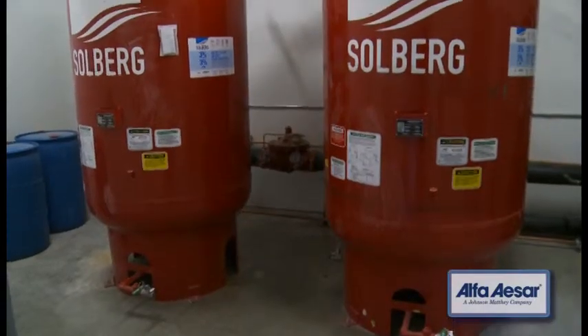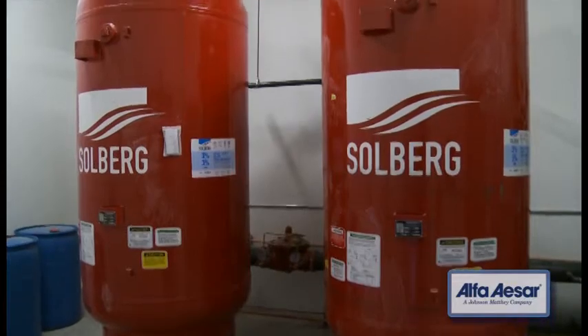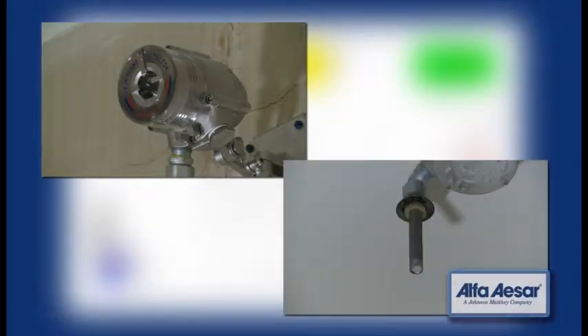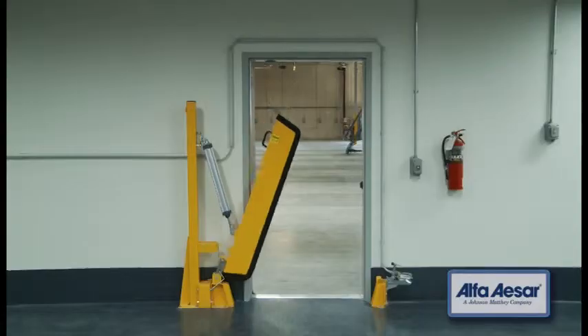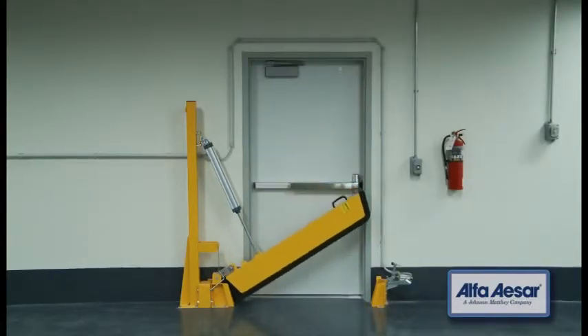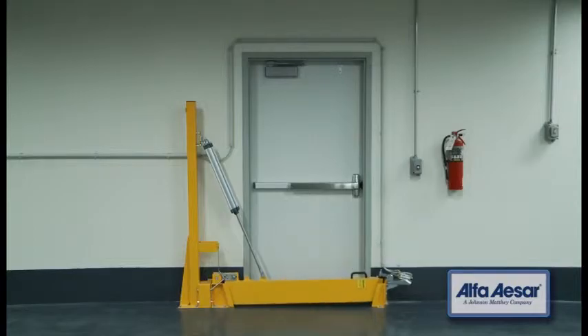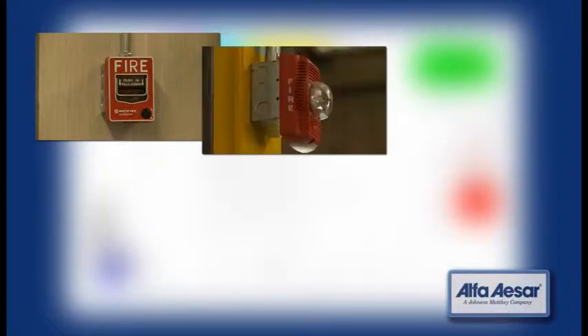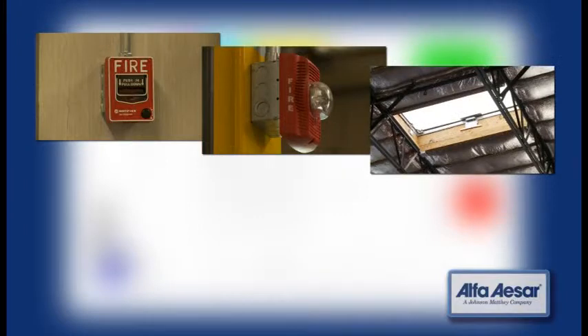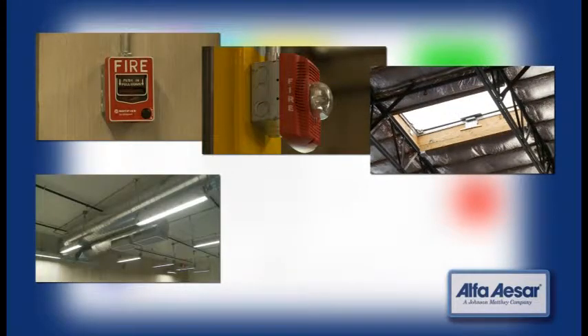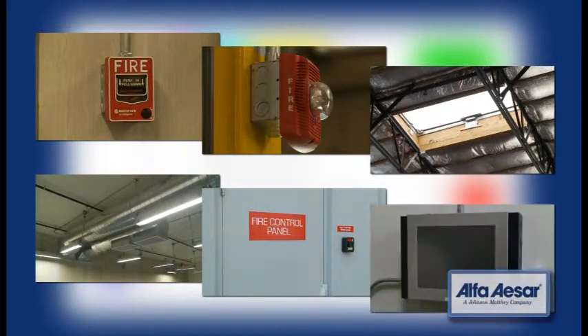The fire suppression system is an AFFF-AR foam system. UV, IR, and flame detectors act as early warning in case of an incident. The building is completely diked, housing a possible 75,000 gallons of liquid. The fire alarm system in the buildings includes manual pull stations at exit discharge locations, audible visual devices for personnel evacuation of the facility, ventilation control, HVAC duct smoke detection, fire sprinkler monitoring, and municipal connection for fire department notification.